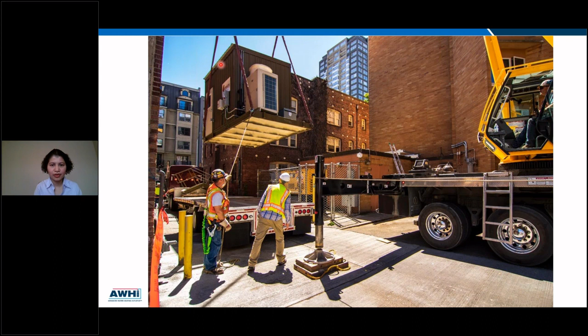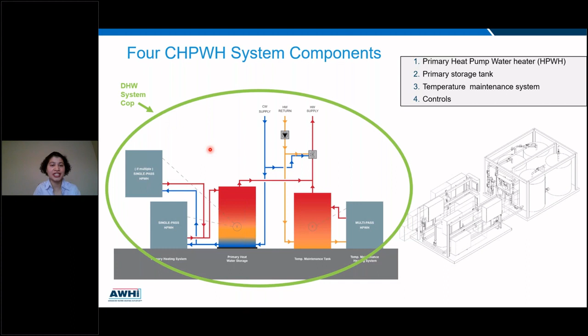Until now, there was just one COP for the actual heat pump water heater piece in central heat pump water heater systems. But with this new approach, what we're proposing is that the heat pump water heaters, the storage tanks, the piping, the controls, and maintenance system will all have an entire domestic hot water system COP. NEEA, the Northwest Energy Efficiency Alliance, now has a specification developed around a system COP, part of their Advanced Water Heating Specification version 8.0.